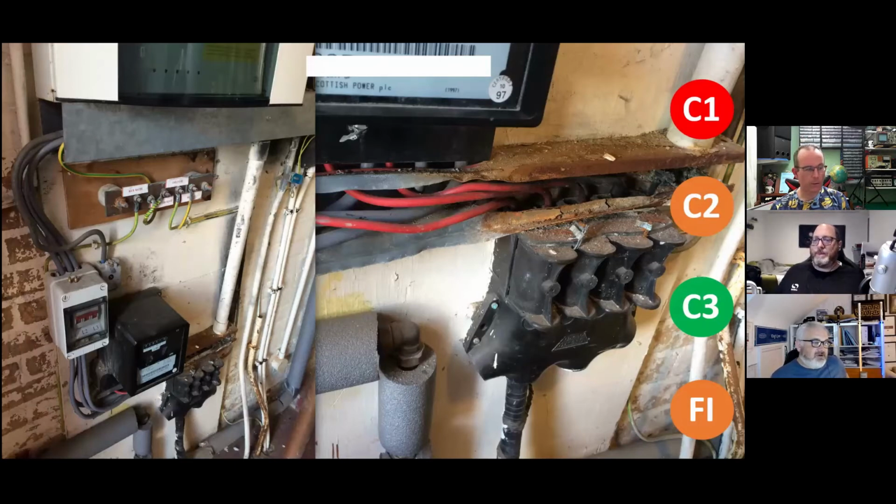And how would you code just that intake? Because let's be honest about it. Every single one of us, when we go into a house, the first thing we do is check the bonding and the earthing. If we don't, we should be leaving. And within 10 minutes of looking at the intake and the board, we generally know whether an installation is going to pass or fail. That's not to preclude us doing the inspection or doing the testing.